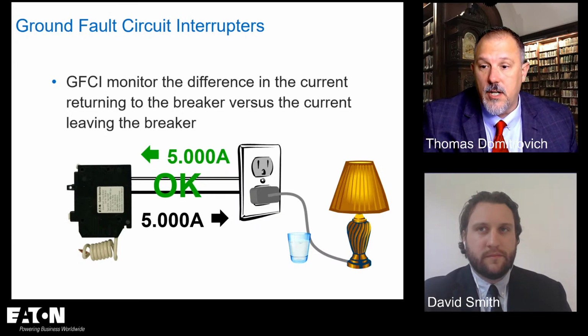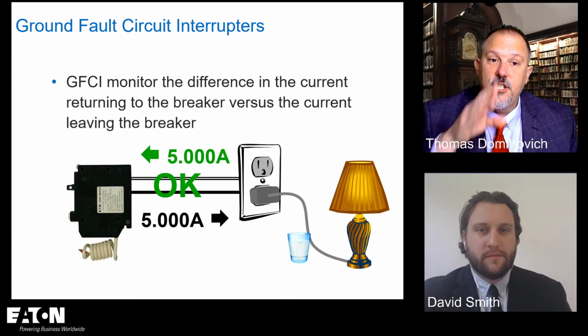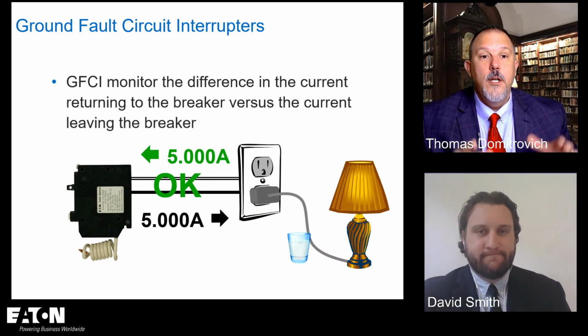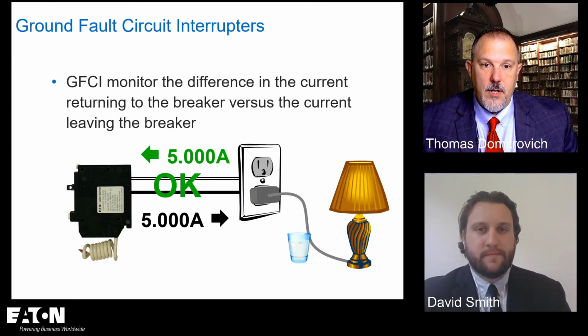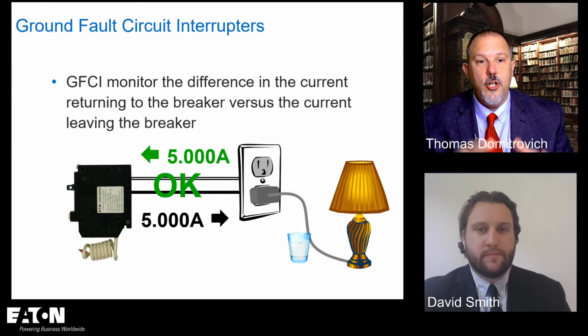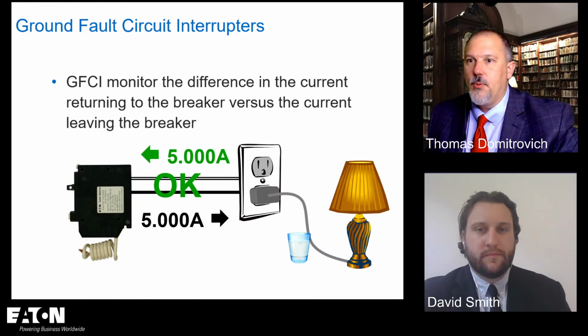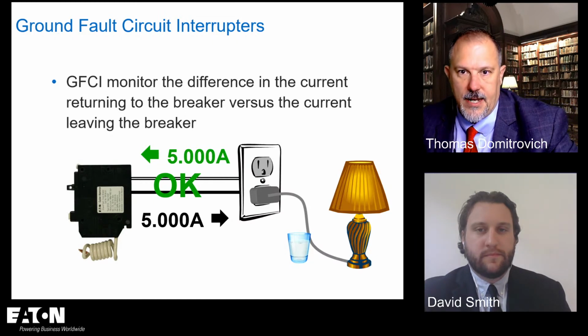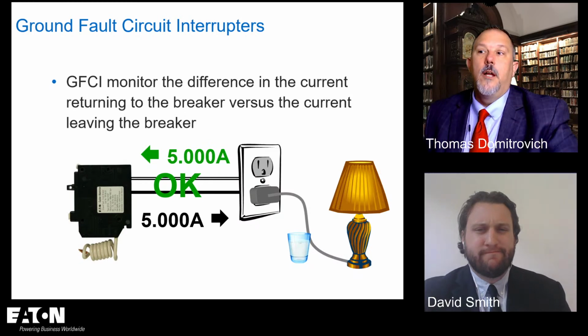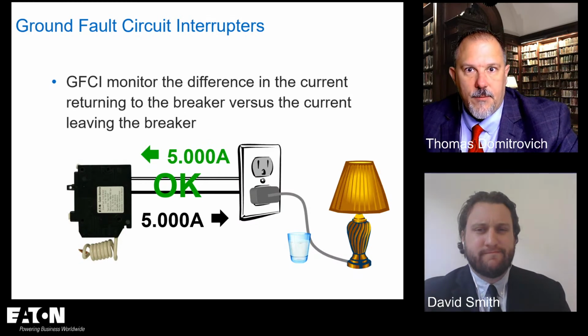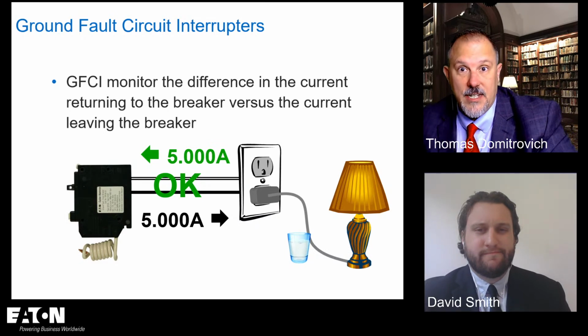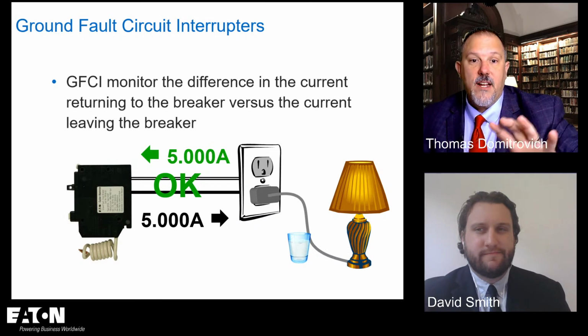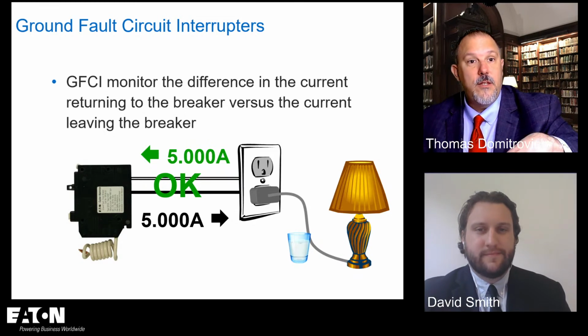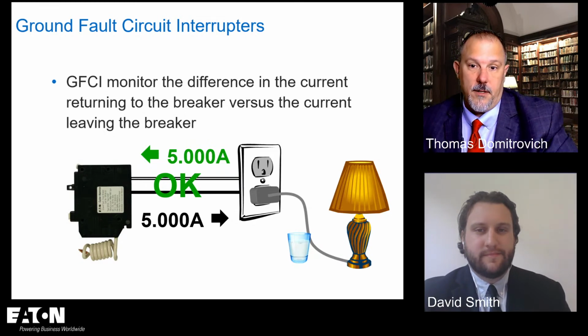So the first thing I want to talk about is the fact that a GFCI and an AFCI do two different things. Okay? So the first hurdle you've got to get past is that I've had people say you can't put a GFCI receptacle downstream of an AFCI circuit breaker, or I can't put an AFCI receptacle downstream of a GFCI circuit breaker. So they go back and forth with those technologies, but in reality, they don't compete with each other.